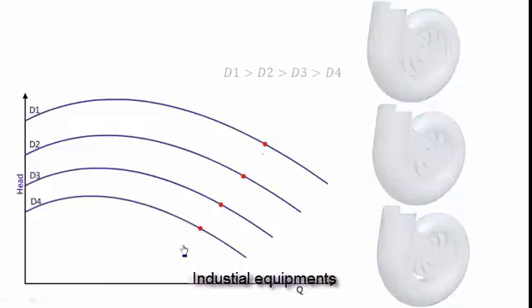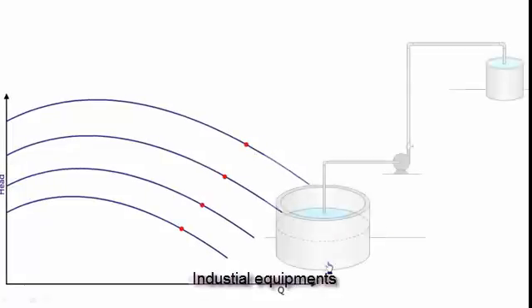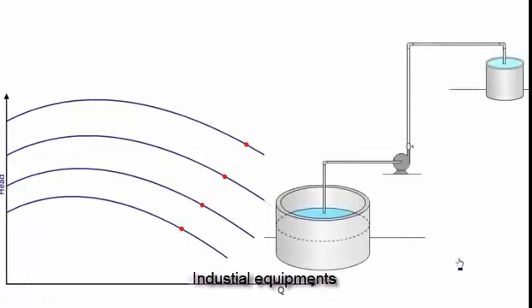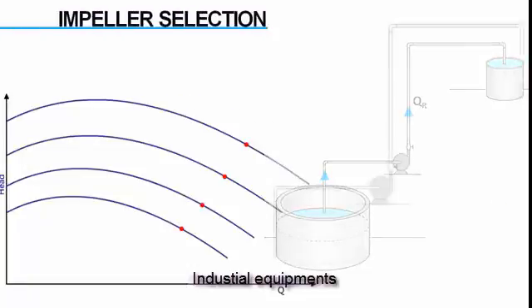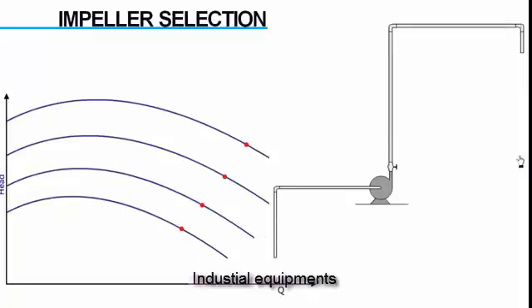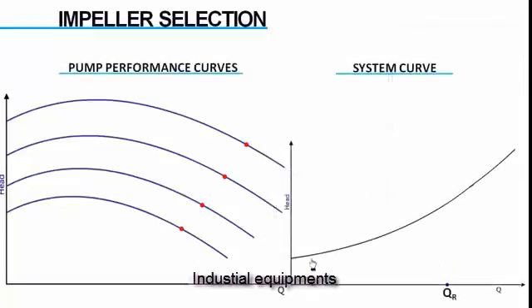So back to the basic question, how to select a centrifugal pump for this application. Main condition is that fluid should be pumped at a particular flow rate to a specified height. Performance characteristics of the system is given in a system curve. That means, how pressure drop varies in system with flow rate. Depending upon minor losses and major losses in network, it would vary like this. Please note that system curve will change drastically depending upon valve opening. Assume this is the system curve at a particular valve opening. Required flow rate is marked here.